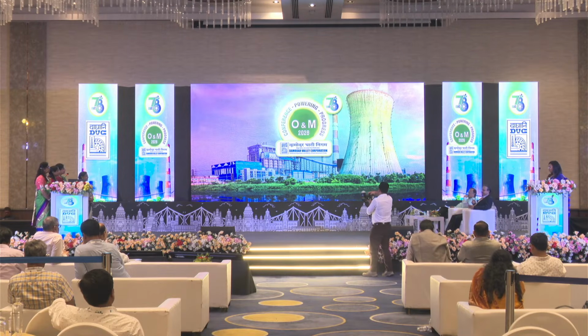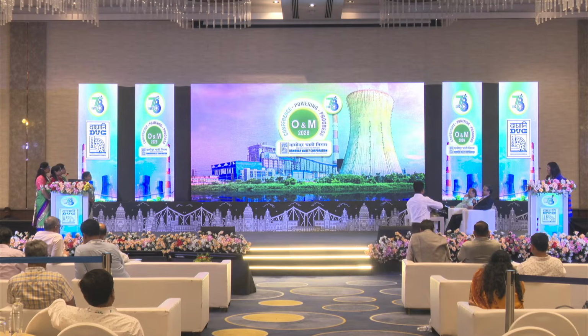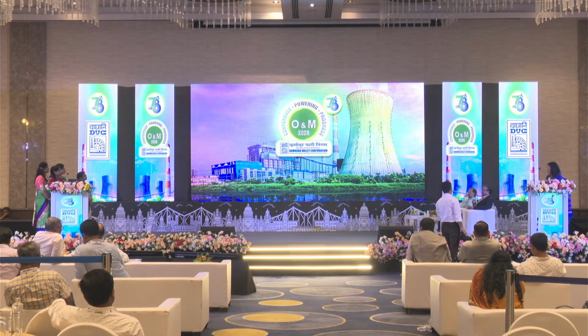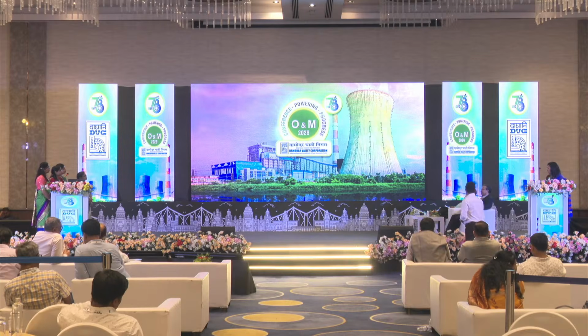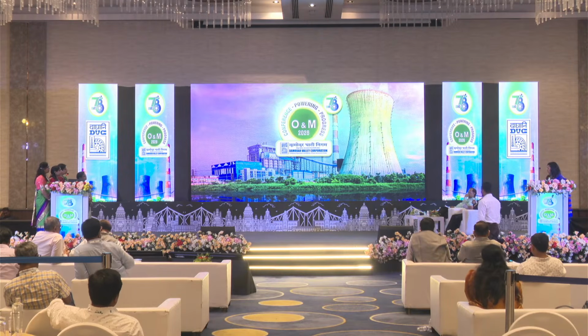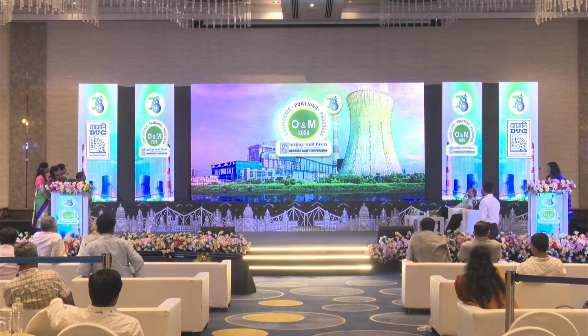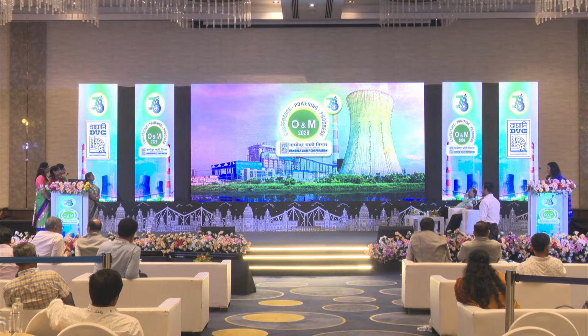And the second is, how many cannons have you procured? Only 1. Is 1 foam cannon sufficient? It's not sufficient. So for your legitimate claim of green energy, you need to increase the number of cannons and spread the spray over the entire coal conveyor. Okay.